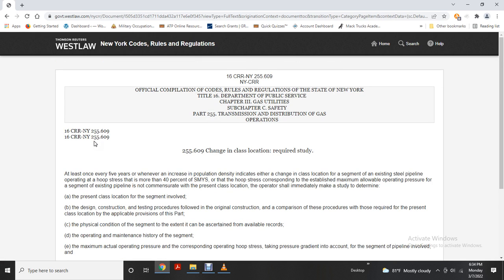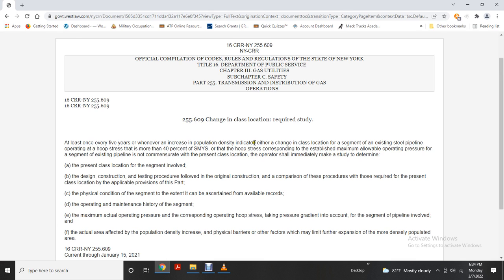Alright, it's 255-609. Change in class and location required study. At least once every 5 years, increase the population density and indicate the change of the class location segment of an existing steel pipeline operating at hoop stress that is more than 40% of the specified minimum yield strength. The hoop stress corresponds with established maximum allowable operating pressure for segment existing pipeline not commensurate with the present class location operation shall immediately study to determine.